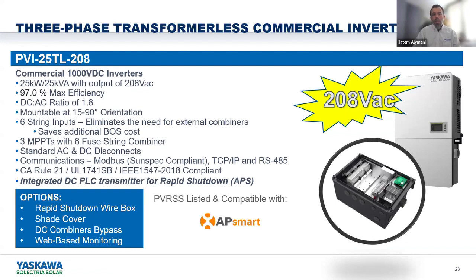The way to understand this is, if you're using our design tool, which we're going to discuss at the end, the design tool is not going to allow you to exceed the DC to AC ratio spec for each inverter. So that's going to be the easiest way for you to make sure that you're not exceeding the DC to AC ratio limitation for the inverter.